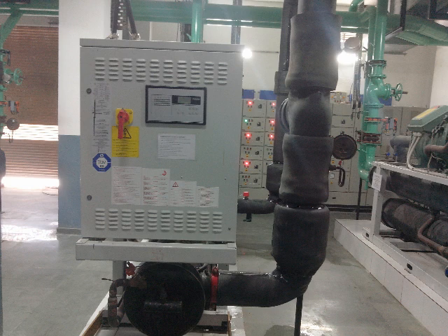This is the main control panel of the chiller. We can set a required outlet temperature of the evaporator and can start and stop the AC plant from this panel. It is monitoring all parameters and displaying them on its unit. It also has safeties like LP, HP, flow switch, under voltage, temperature safeties and overload safety. It will trip the compressor if a safety limit is crossed.